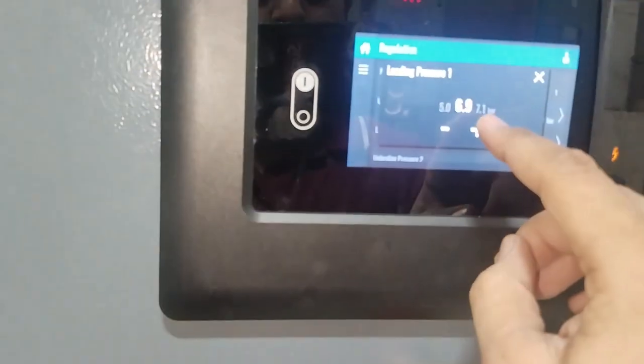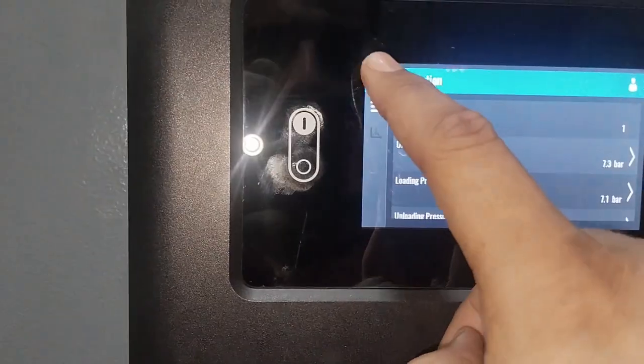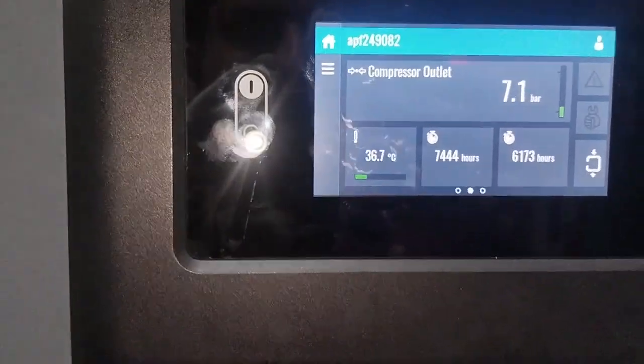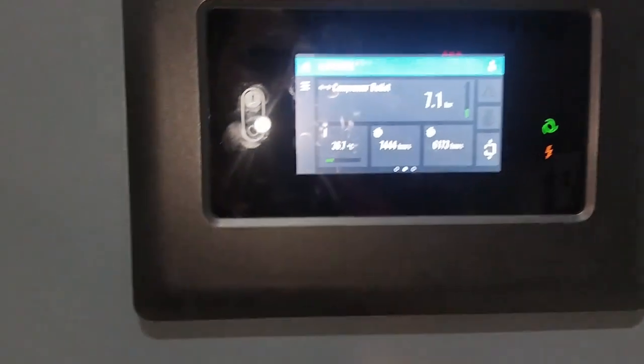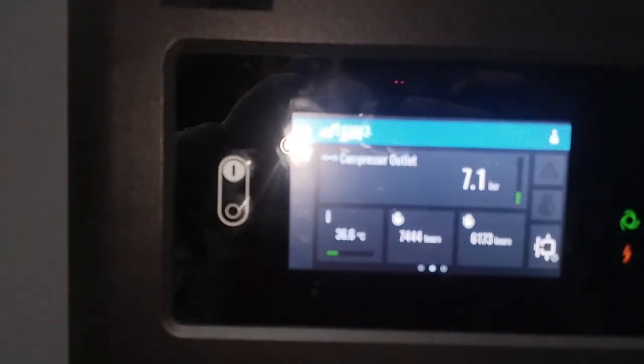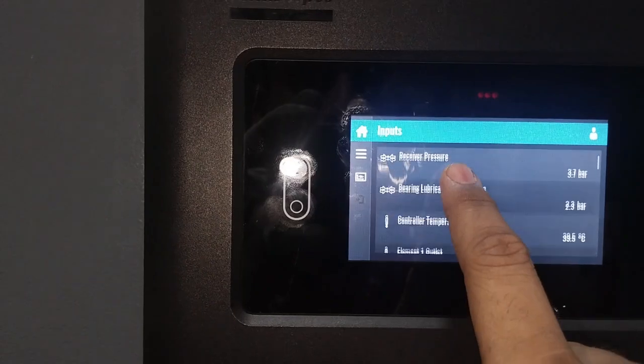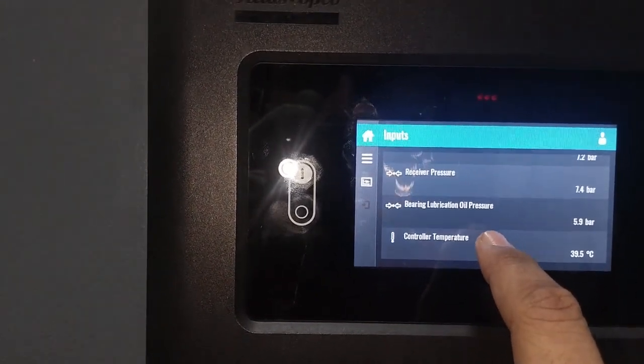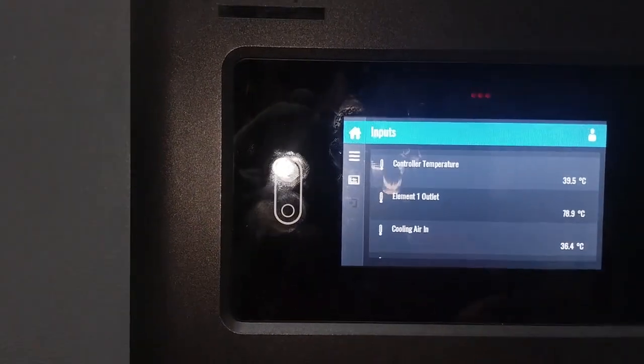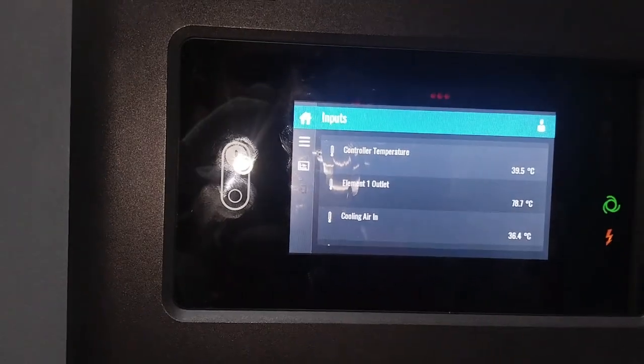The unloading point is set to 7.2 bar and the loading point to 7 bar. The compressor has now been started — I will show you all the parameters while it is in running condition. The compressor is working fine. All parameters of the compressor are under limits. You can check that element one outlet temperature is now 79 degrees. After starting the compressor, touch the filter — if it is hot, it means the filter is passing oil properly. Check all parameters; all parameters are normal.